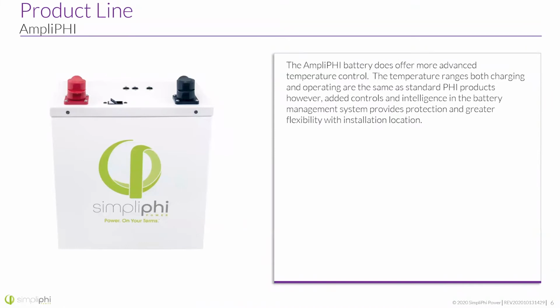The AmpliPhi, this is our comms-based battery. This battery does have a little bit more of an intelligent design put into it with the temperature control functions. So the AmpliPhi battery does offer temperature control. The temperature ranges, both charging and operating, are the same as the standard Phi. However, basically what this allows for is a safeguard against charging when the temperature is too low or too high. It won't heat or cool the battery more than any other battery would. It just simply says, if the temperature goes to this temperature, either ramp down charging or make sure the charging does not happen.